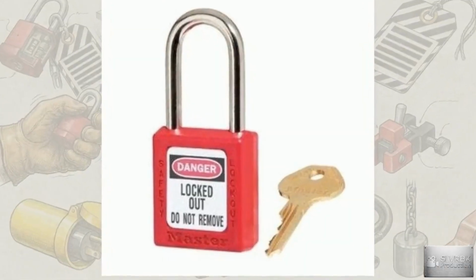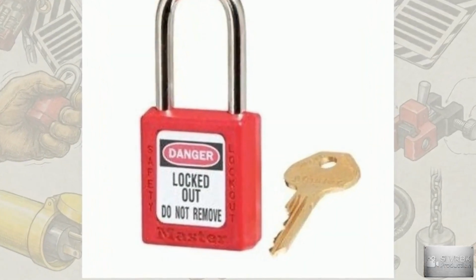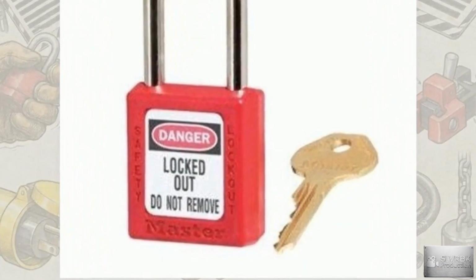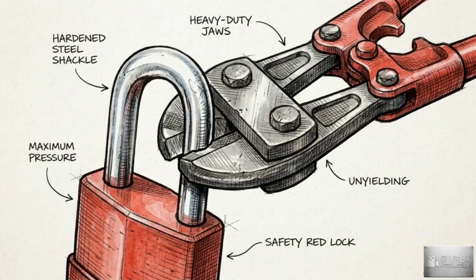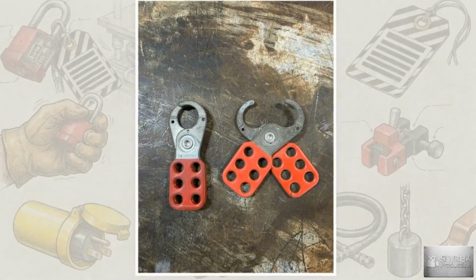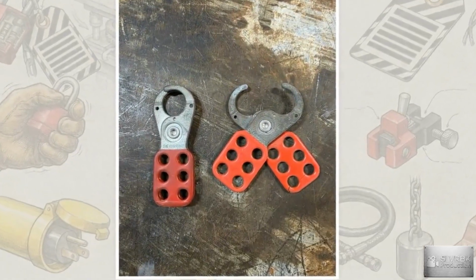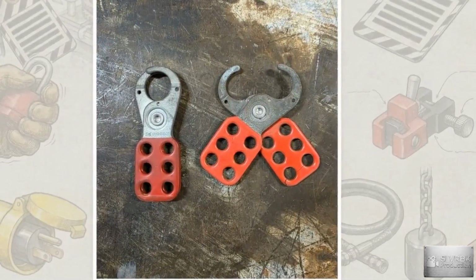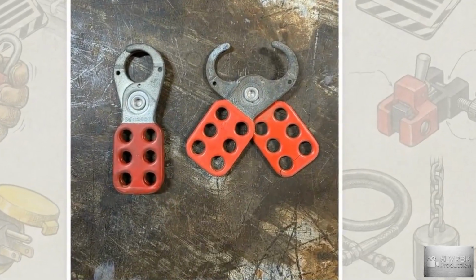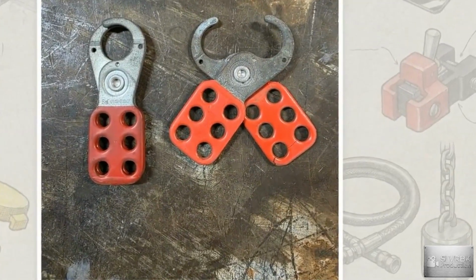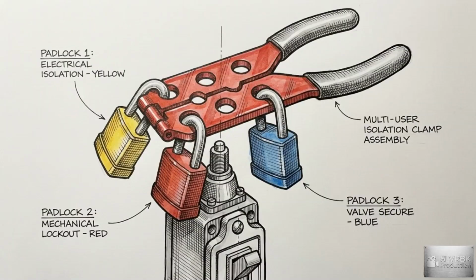The final layer of restraint is the lock itself. To be compliant, a safety padlock must be substantial enough that removing it without a key requires excessive force and specialized metal cutting tools, like bolt cutters. When multiple technicians are servicing the same equipment, they use gang clamps. These multi-hole hasps require every single worker to attach their personal lock, ensuring the system cannot be re-energized until the final person finishes their job and leaves the area.